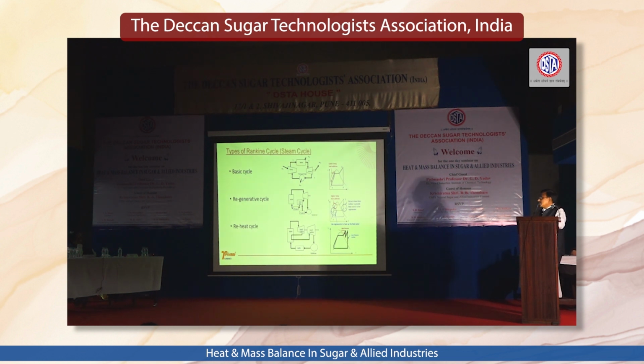The third Rankine cycle is the reheat cycle. It is mainly used in 70 megawatt or larger power plants, or normally utility power plants like NTPC. There, steam is taken from the boiler at a mid section and fed back into the turbine at its mid section, reheating the steam. This gives more enthalpy, which is converted into mechanical power, giving some more power. This reheat cycle is the highest technological invention, mainly useful in utility power plants of say 200 megawatt, 600 megawatt and above, and definitely in industrial cycles above 70 megawatt.